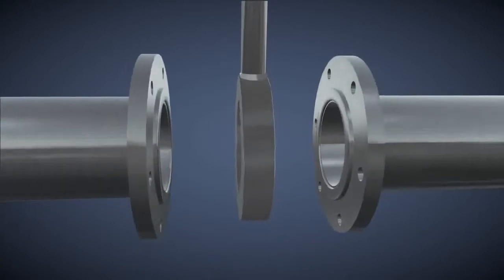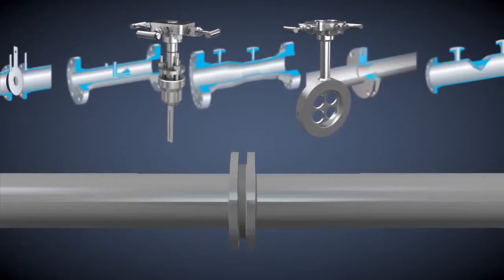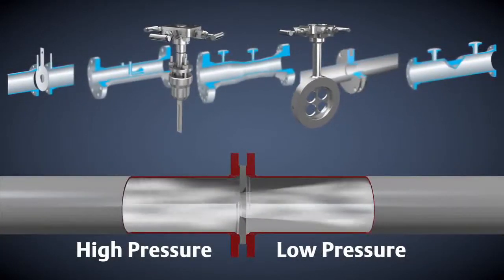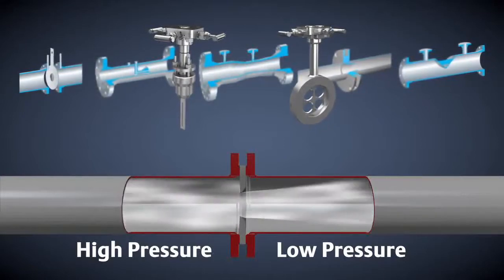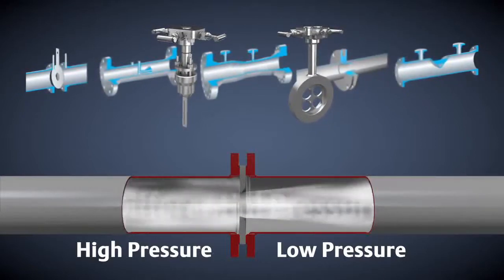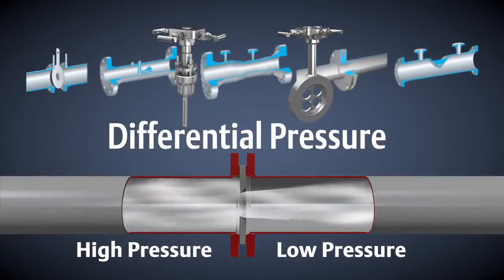Primary element selection is dependent on process conditions. All of these different primary elements have one thing in common. They constrict the flow in a pipe, causing a pressure drop from one side to the other. The difference in pressures is the differential pressure. The square root of DP is proportional to the flow rate.